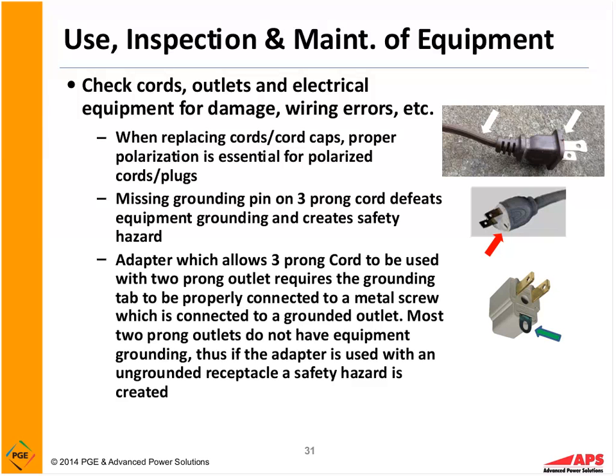The picture down below it here, we can see that the ground pin is missing. Where the red arrow is, the ground pin is missing. So with any kind of fault in portable equipment, or anything that we use where that ground pin is missing, there is a hazard. And some of you may even have an older home where you may buy something that actually has a three-wire cord, but yet you only have a two-wire receptacle.